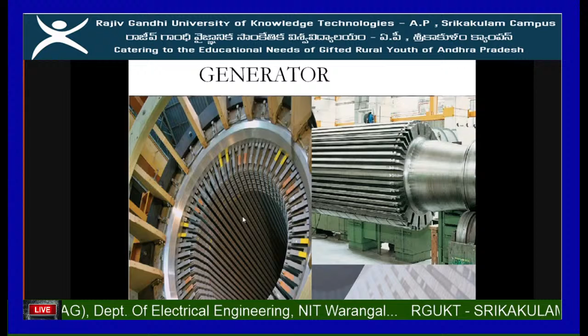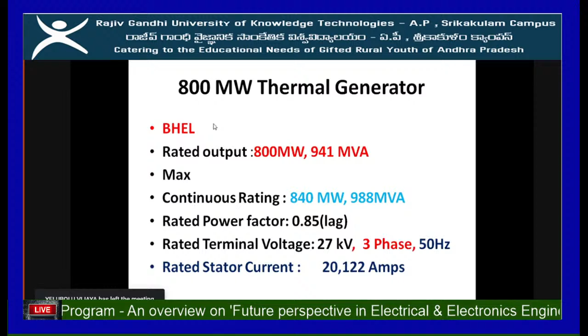So you can look at the rating: 800 megawatt, 941 MVA, BHEL make. It's 800 megawatt, continuous rating up to 840, you can load it. Power factor is 0.85, and the biggest voltage available is 27 kV. Normally it goes up to 21 kV, and as I told you, the stator current is now increased to 20,122 amperes.